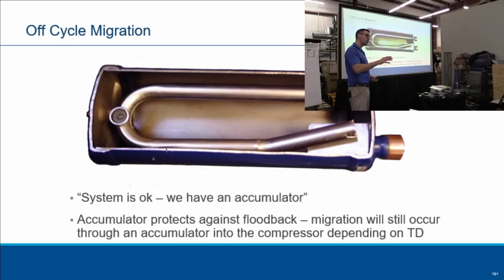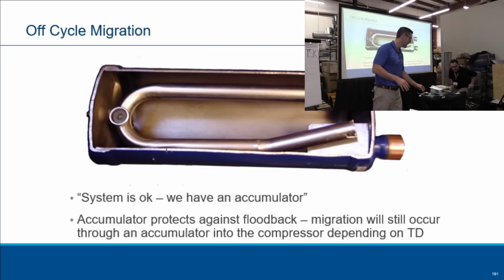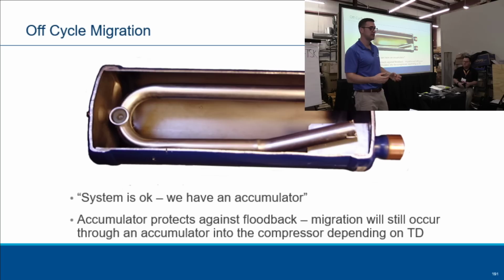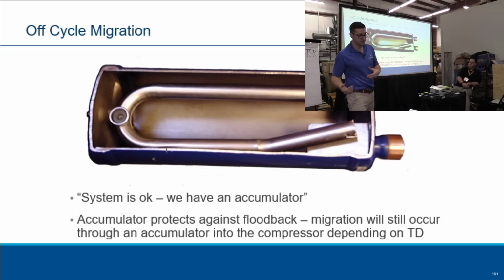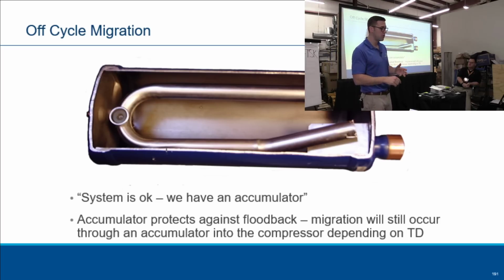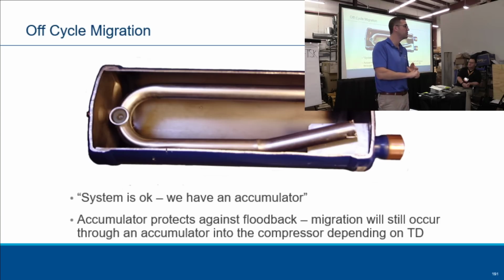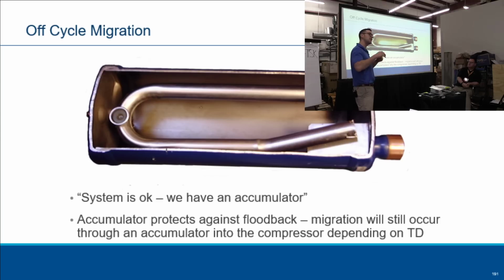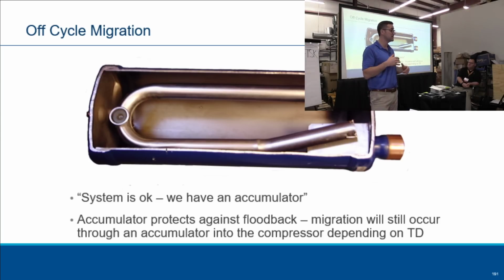Another really important point, and I got caught on this when I was a mechanic too. Had a 5-ton system, went up, a compressor had failed. It was a bad electrical burn. You could see the oil, you could smell it. So I pulled out the compressor, got a new compressor, pulled it down below 500 to hold it, put a new filter dryer on it, an acid burn filter dryer, did all of this, and I thought I did such a great job. It took me a couple hours longer than the job quoted for, but I'm like, wow, I did a good job.